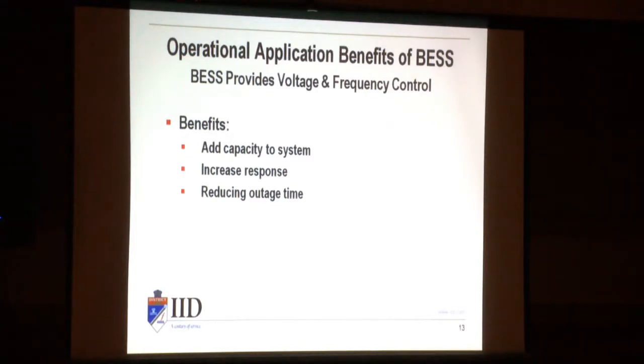And when they lost those lines, they'd have to rely on their gas and oil units. Most of the time they'd have to leave them running, because if they went out, you'd be black starting everything — you'd have to shut everything down to start it back up. So leaving those running is very expensive. They went ahead and put in a battery system about 10 to 15 years ago, and saved their customers millions and millions of dollars by shutting those units down.